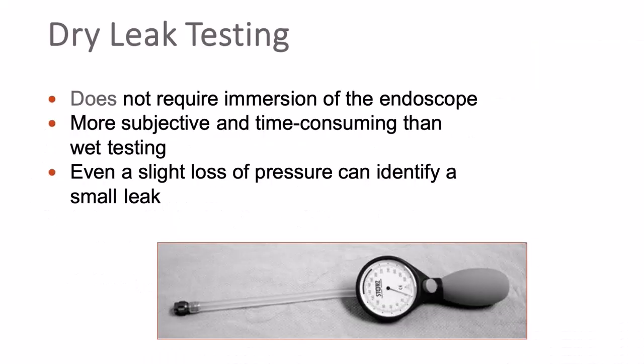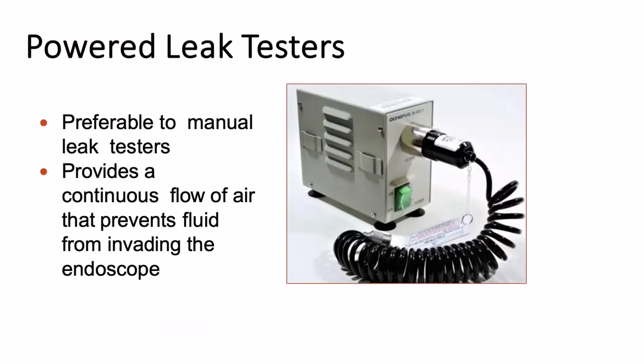Dry leak testing does not require immersion of the endoscope, but it's more subjective and more time-consuming than wet testing. Even a slight loss of pressure can identify a small leak, but if you follow the instructions, you will not have a problem. Powered leak testers are preferable to manual leak testers. They provide a continuous flow of air that prevents fluid from invading the endoscope.